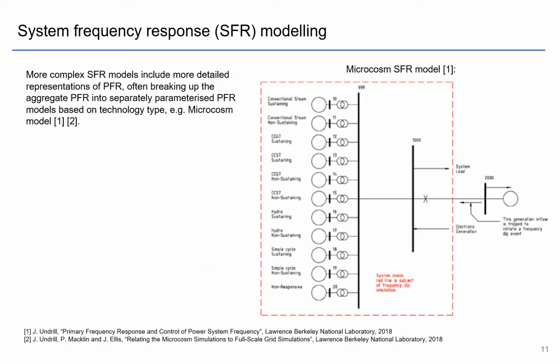I've described a few simpler SFR models that have analytical closed form solutions, but the more complex SFR models out there include much more detailed representations of the PFR. So rather than just aggregating all of the PFR as a lead lag block or just a first order lag block, the more complex models separate all the PFR into separate units or groups of units, usually by technology type, which is what the Microcosm model does. And you can see here that they've separated out the steam turbines from the combined cycle gas turbines, from hydro, from open cycle gas turbines, and so forth. And so each of these separate models have their own parameters and possibly even variations on the dynamic model themselves.